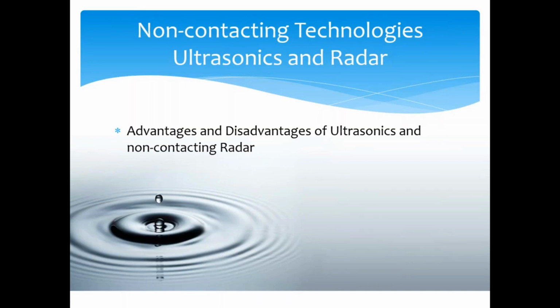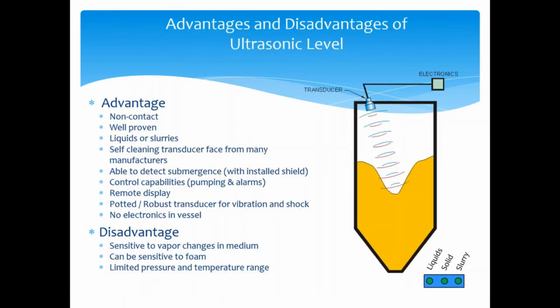Okay. So just real quick, advantages and disadvantages of both. I mean, we've talked about a lot of these specifically already, but again, advantages of ultrasonic, just across the board, well proven, been around a very long time, non-contacting, can do liquid slurries, or in some cases might be able to do some solids. Self-cleaning transducer face for many manufacturers. That's because the face of this transducer actually vibrates as we're sending that signal out. And disadvantages are going to be sensitive to vapors instead of air, foam, and then pressure and temperature ranges or gradients.